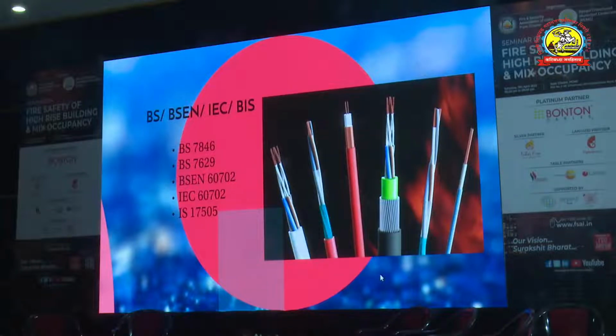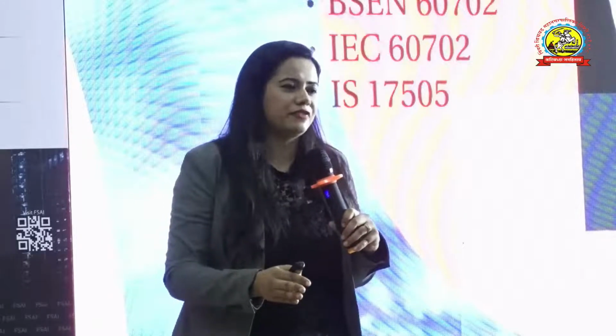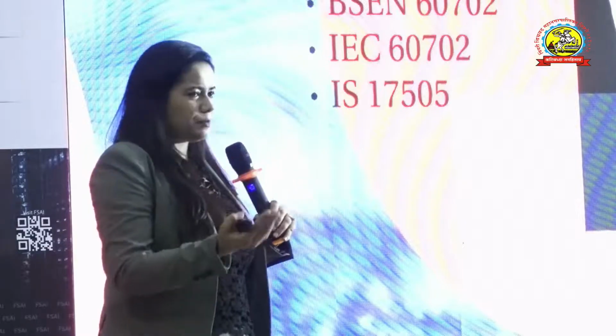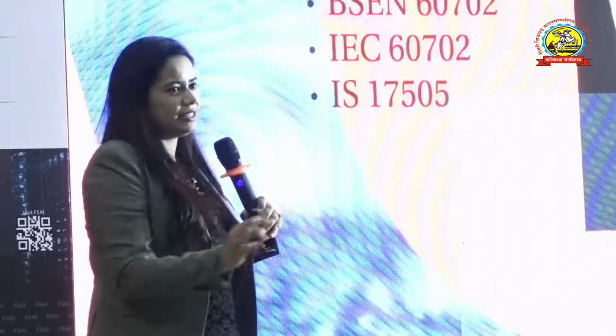Another loophole is that all these standards are purely copper, and it's highly recommended to use fire survival cables in copper. But those in the industry know it becomes very expensive. So we have an alternative in aluminum, although it isn't in either of these standards. We can do 25 square mm and above aluminum fire survival cables, but as per customer requirement, not as per any standards.